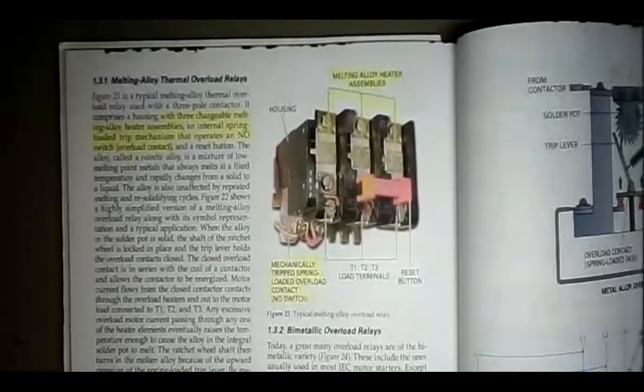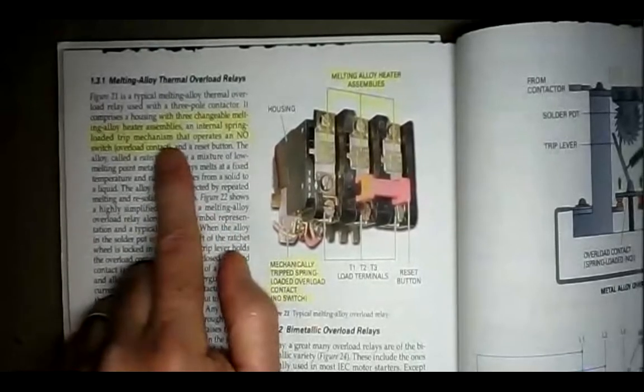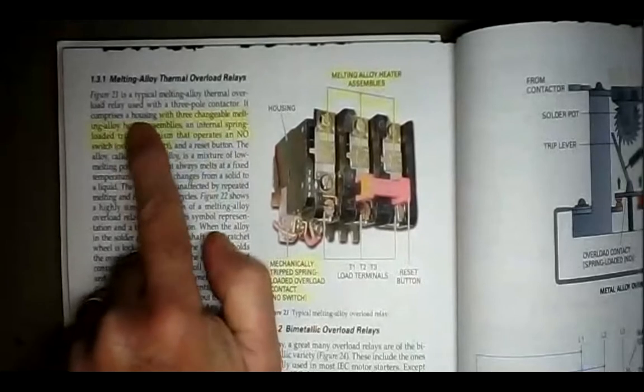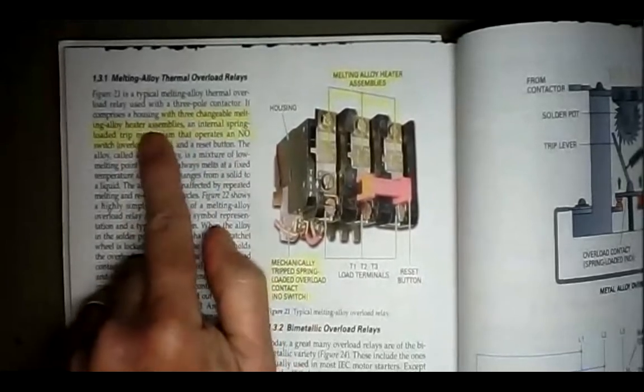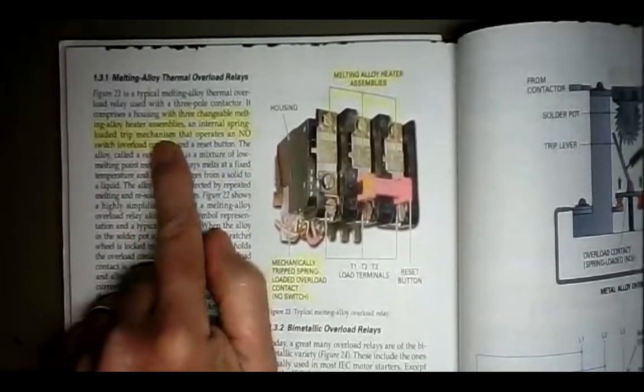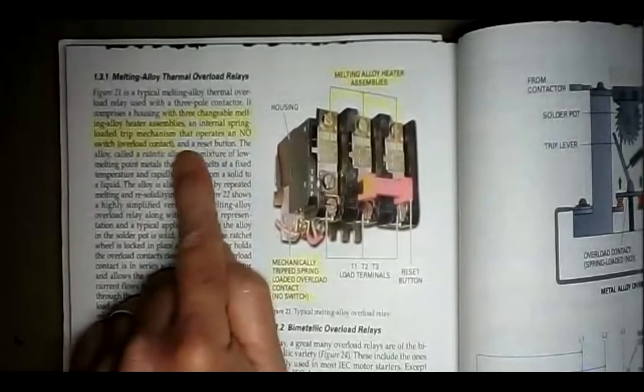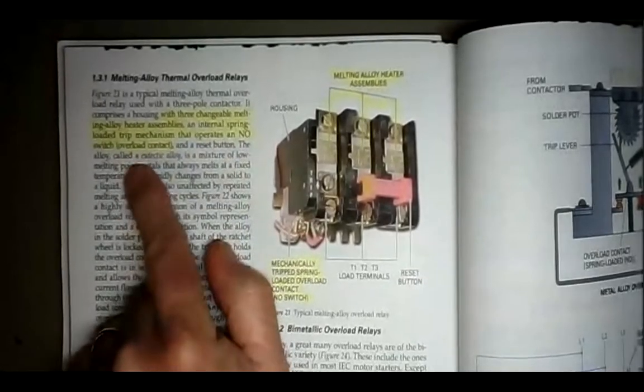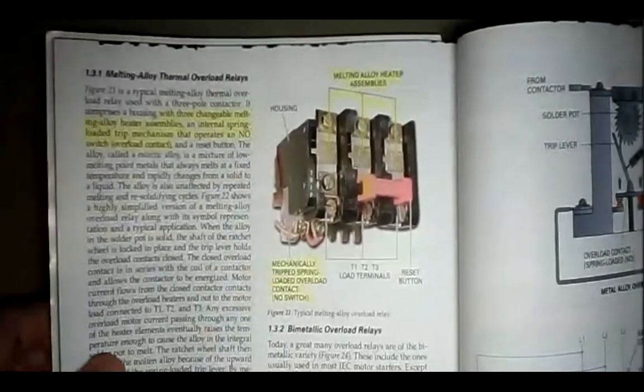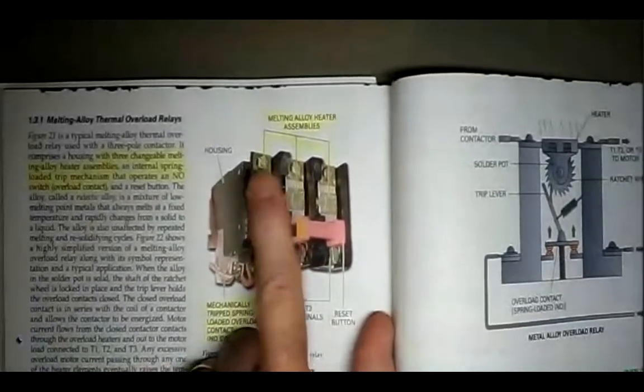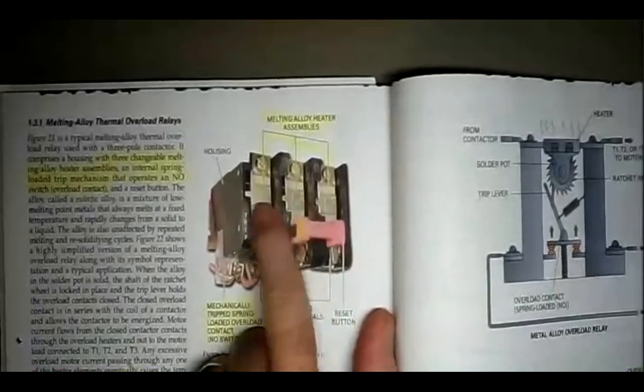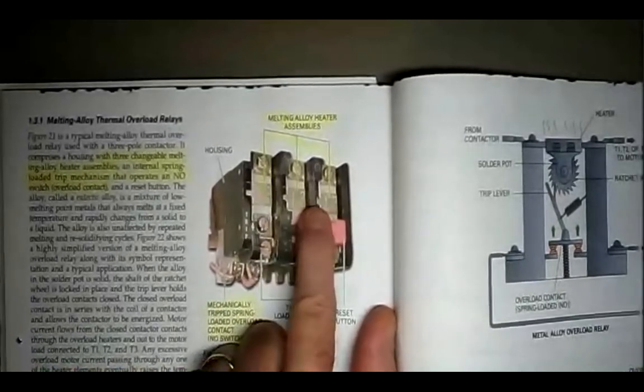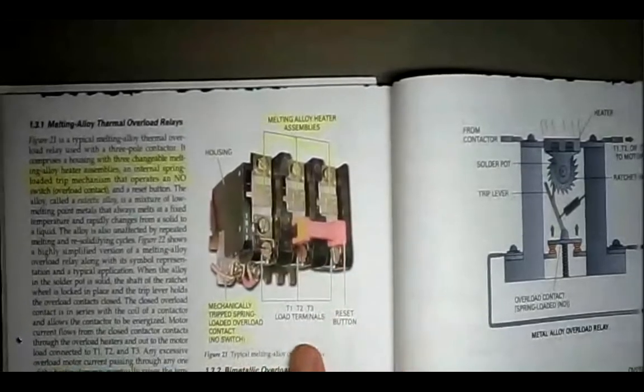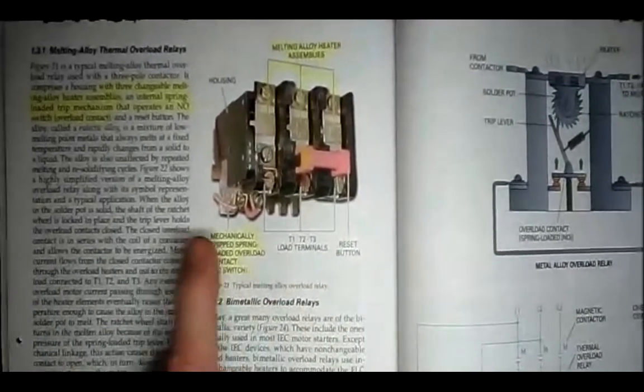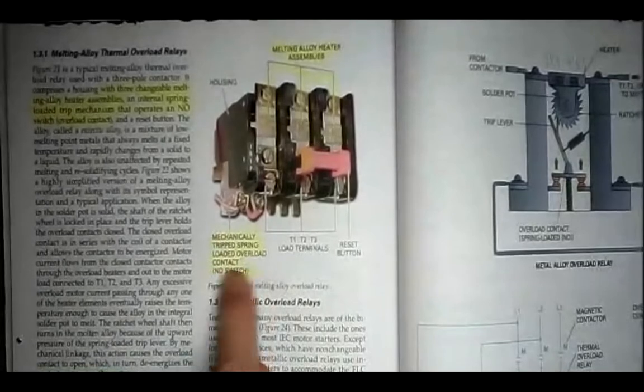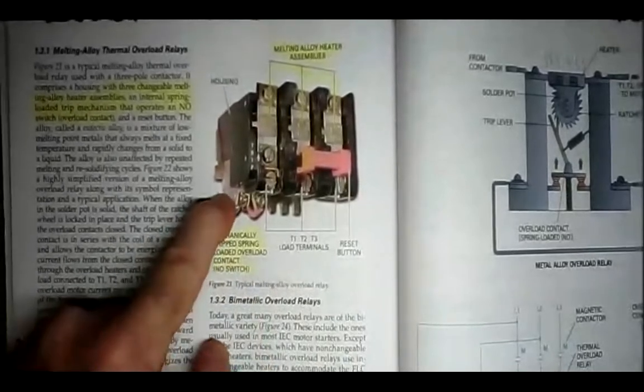Melting alloy thermal overload relays. It says figure 21 is a typical melting alloy thermal overload relay used with a 3-pole contactor. It comprises a housing with 3 changeable melting alloy heater assemblies, an internal spring-loaded trip mechanism that operates a normally open switch, overload contact, and a reset button. So these are your heaters, 1, 2, and 3. The full current of the motor goes through those 3 heaters, and they are exactly what they sound like. They're a heater. They heat up when you have the presence of current flowing through them. And here's the mechanically tripped spring-loaded overload contact. The normally open switch is down here.